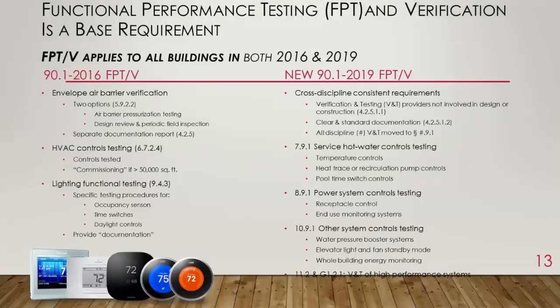Then in the power system, there are requirements for receptacle control in several building types, that those would be verified to be functioning properly, and that the end use monitoring systems would be checked out as well. Also in the other systems, we looked at water pressure booster systems requiring some commissioning check. There are some elevator light and fan standby mode controls that now are listed as requiring testing, and where it's required, whole building energy monitoring would require testing.